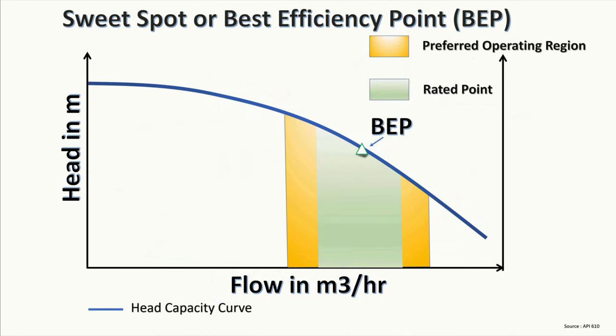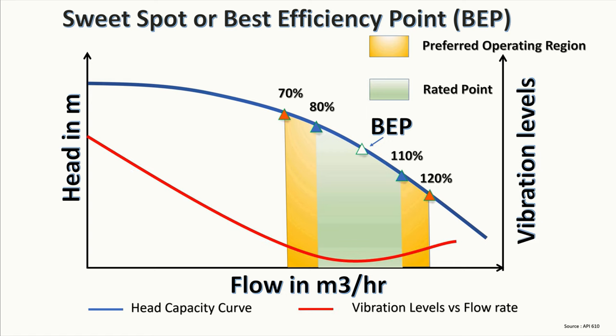Tip number one: try to operate the pump around its sweet spot. There is a reason why API 610 — a widely recognized standard for pumps in oil and gas service — recommends the operating point to be within 80 to 110% of the BEP as the preferred operating range, and within 70 to 120% as the allowable range. The nearer the operating point to BEP, the better the performance and the fewer the cavitation issues.